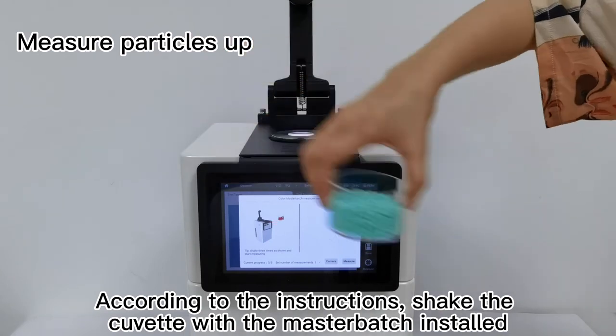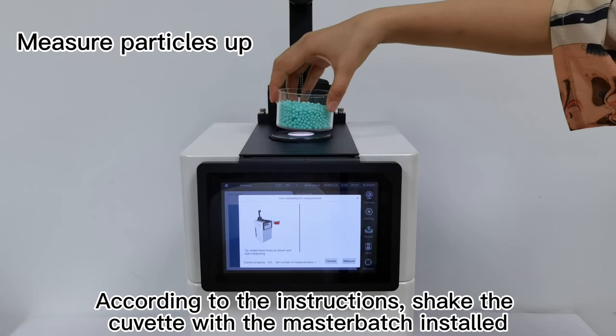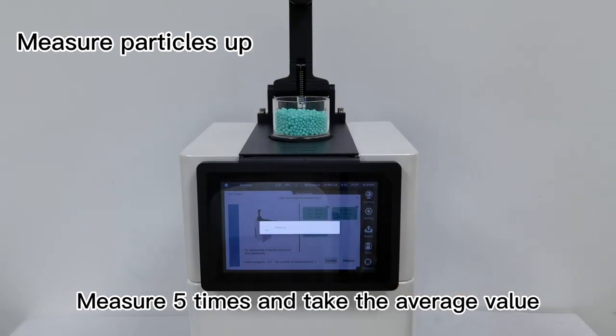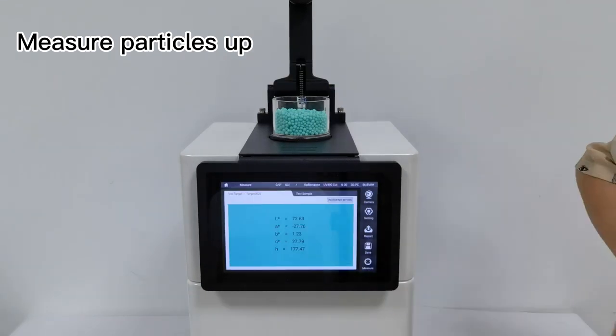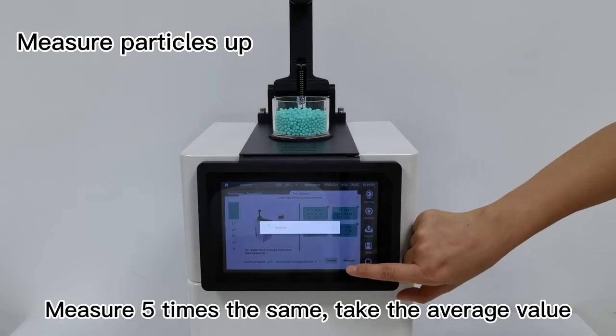According to the instructions, shake the cuvette with the master batch installed. Measure 5 times and take the average value. Switching to sample measurement, measure 5 times the same and take the average value.